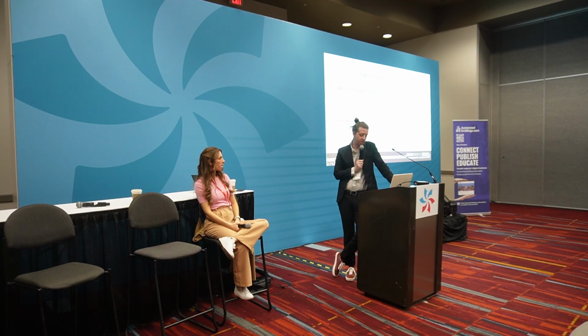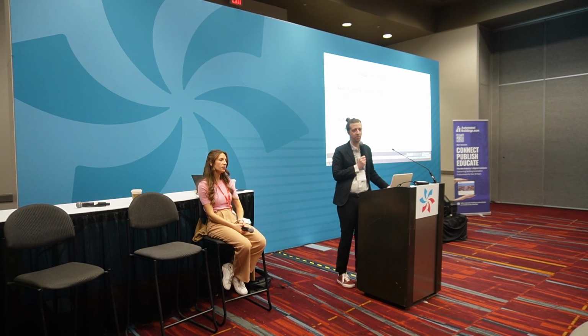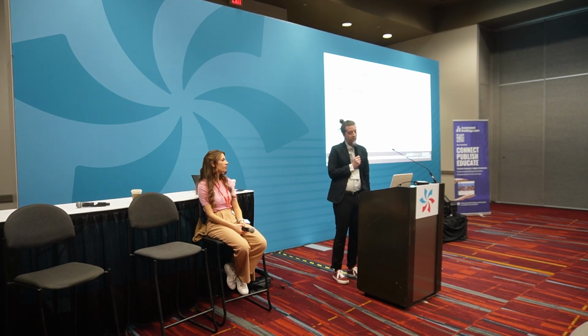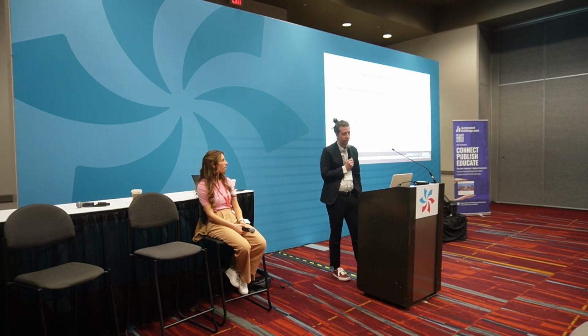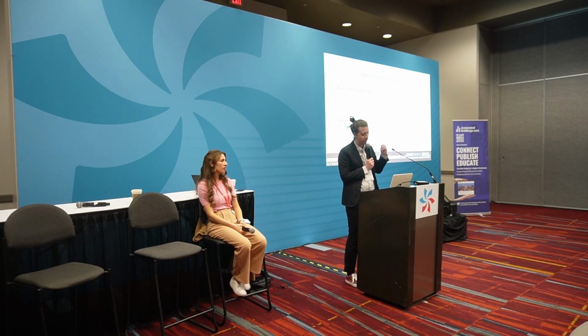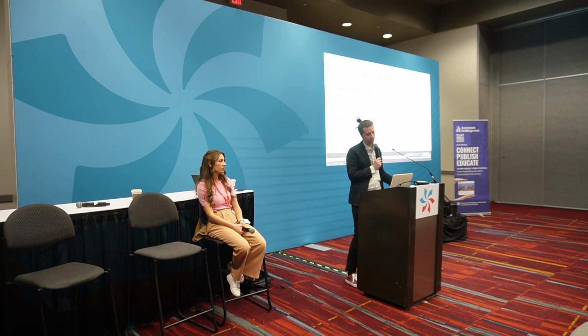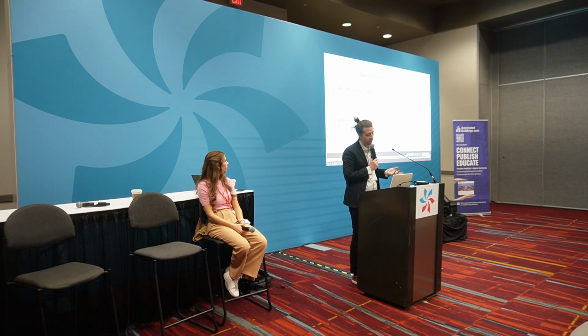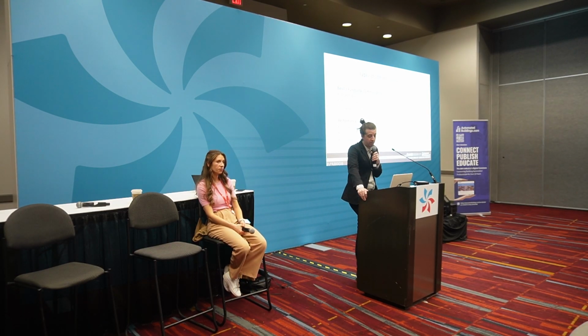There's retro commissioning, recommissioning, continuous commissioning, all kinds of different terms referring to different things. The quick answer, our rule of thumb, is every 5 years at a minimum for retro commissioning. Recommissioning means going back and redoing something that has already been commissioned. Retro commissioning usually refers to going back to systems that were never commissioned. There's a lot of overlap in those terms, but they're inherently a performance commissioning process in its purest form, because you're going back and finding performance faults: leaking valves, bad sensors, sequences of operation that aren't working well, condensing boilers not condensing because hot water temperatures are too high, chillers short cycling, stuff like that.